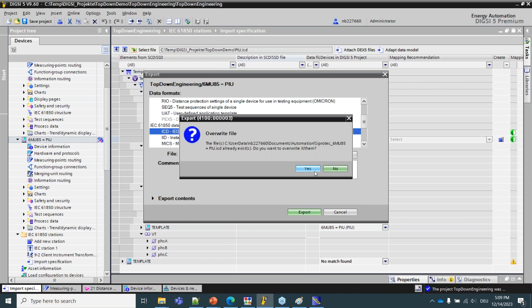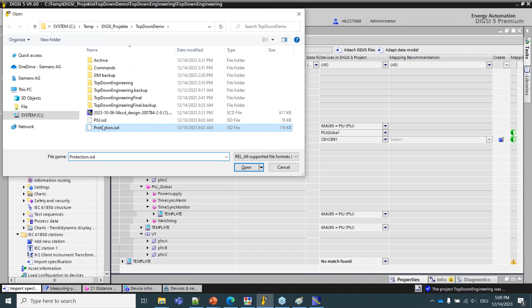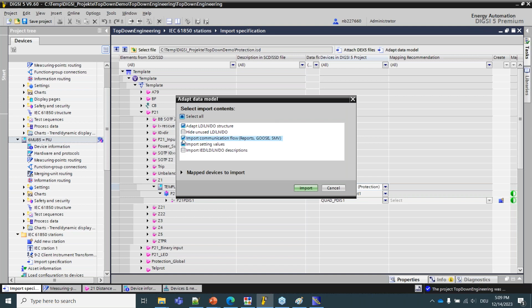The same process can then be repeated for the protection device. For the protection device, I just select the protection ISD file, and same procedure. I have there a distance protection function with a first zone. I select the device where that functionality is realized, and that functionality is realized as stated in the distance protection function. I map all the signals the same way, adapt the data model again, and export the process ICD file so that I can hand over to Yannick for the next step of the presentation.